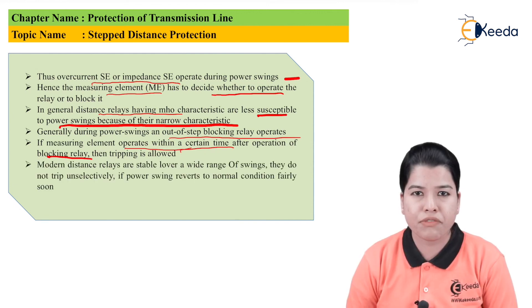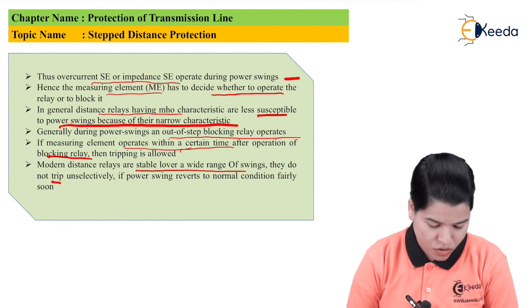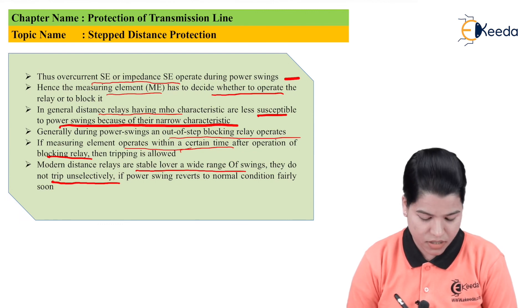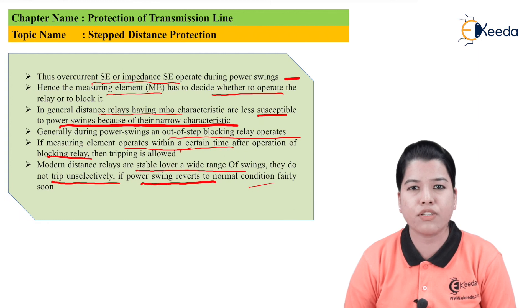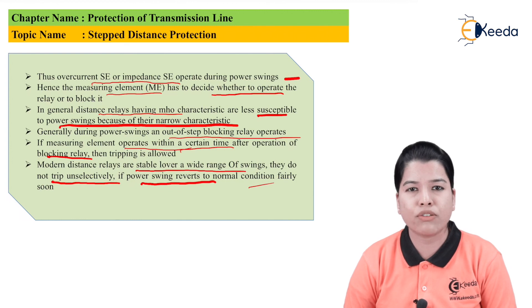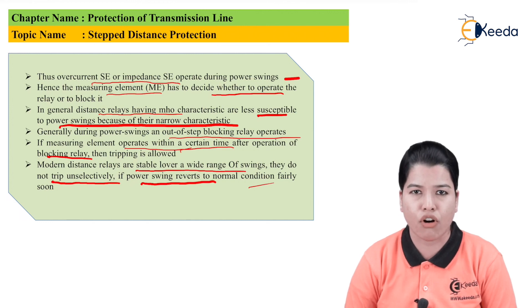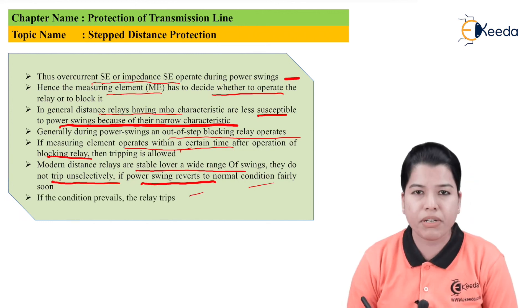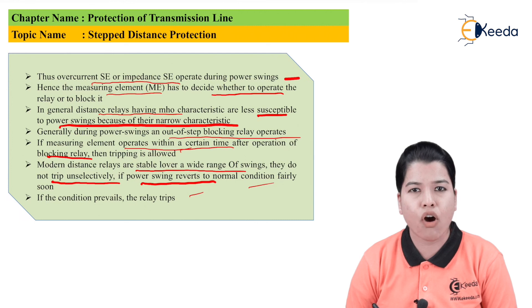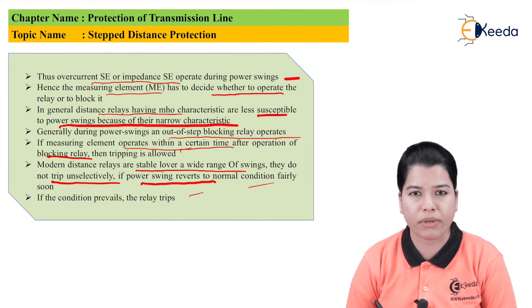Modern distance relays are stable over a wide range of swings and do not trip unselectively if the power swings revert to normal conditions fairly soon. Power swings are only present for a small period of time, after which they return to normal. The relay must decide whether to trip or not. For heavy power swings, the relay should operate, but a power swing of very short duration should not be considered a fault. Only if the condition persists — that is, if power swings keep recurring or have very high magnitude — will the relay operate.